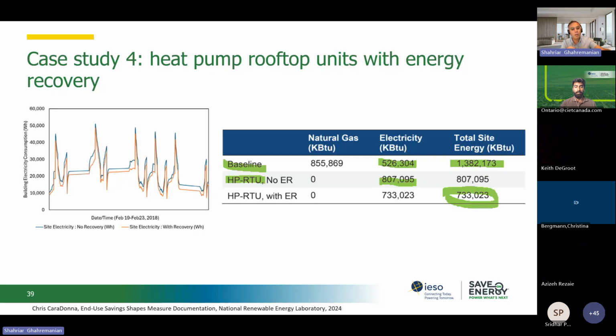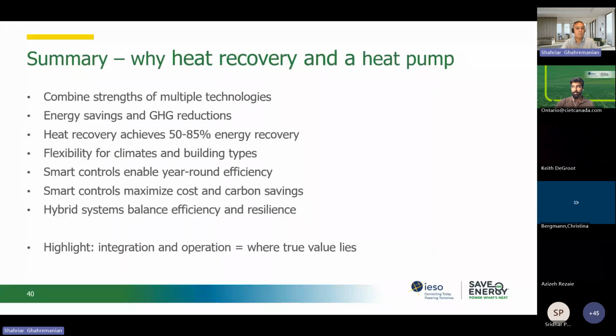So again, investing in a heat pump and then adding energy recovery to that, we can benefit from that. And this is the profile for typical days in, let's say, February, showing a typical load and the differences between each of these three systems. For sure, the difference between no energy recovery and energy recovery heat pump RTUs is minimal compared to the natural gas burning one. But if you multiply it by, let's say, 10 years, 20 years, then it becomes a lot bigger value, especially in areas like ours where electricity is not cheap, so it's expensive.